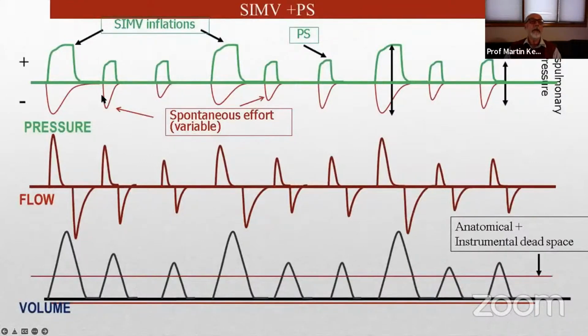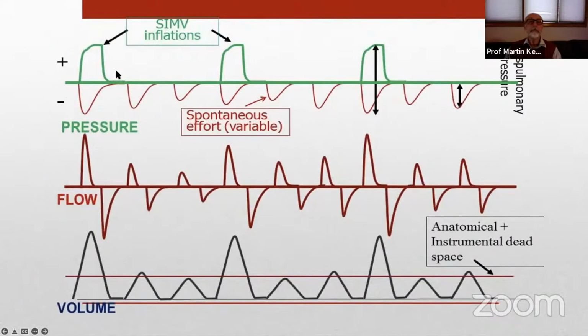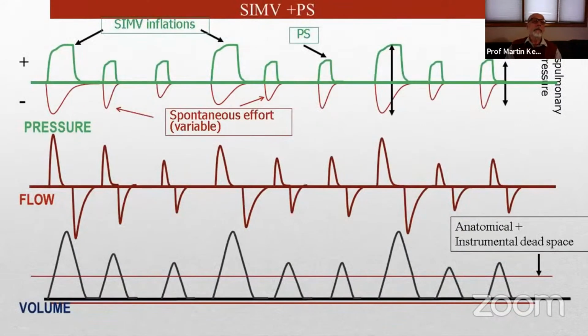And this is shown here. Again, very much the same breathing pattern of the infant. But now we have added, apologies, this is jumping on me. Now we have added some positive pressure support, so that the tidal volumes become more adequate and easily clear dead space. So it's important to recognize that breathing through a narrow endotracheal tube really handicaps our extremely small infants. And because without adequate pressure support, there are only a relatively small number of positive pressure inflations, the tidal volume with SIMV ends up being larger and more injurious than with assist control, and that's been pretty well documented.